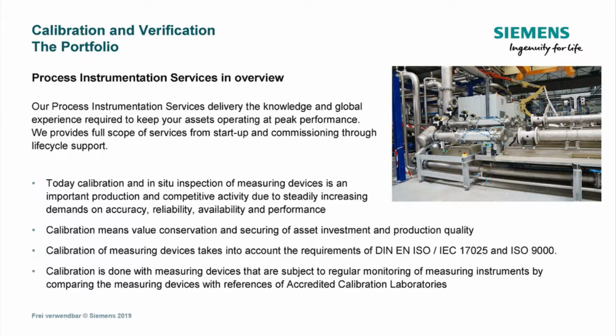Today, calibration and in situ inspection of measuring devices is an important production and competitive activity due to steadily increasing demands on accuracy, reliability, availability and performance. Calibration means value, conservation, and securing of asset investment and production quality. Calibration of measuring devices takes into account the requirements of DIN, EN, ISO, IEC 17025 and ISO 9000. Calibration is done with measuring devices that are subject to regular monitoring of measuring instruments, by comparing the measuring devices with references of accredited calibration laboratories.